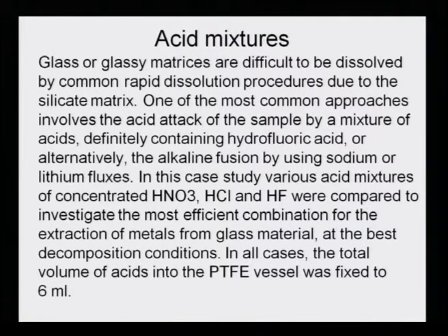In all cases, the total volume of acid in these Teflon PTFE vessels was fixed to 6 ml. It cannot exceed more than 6 ml because the vessels are slightly big, but there has to be a vacuum space to be able to handle the pressures of the gas that are generated out of these acids. They are not all in liquid form, some of them are also in the vapor form, and if the liquid volume becomes large, then the total space that would be left will be small.